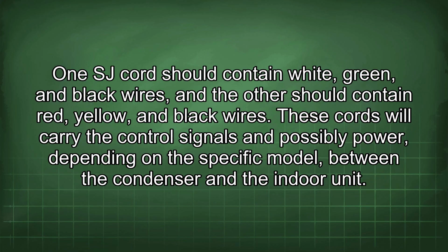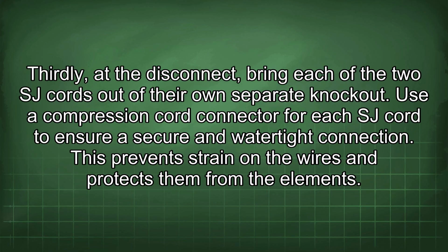indoor unit. Thirdly, at the disconnect, bring each of the two SJ cords out of their own separate knockout. Use a compression cord connector for each SJ cord to ensure a secure and watertight connection. This prevents strain on the wires and protects them from the elements.